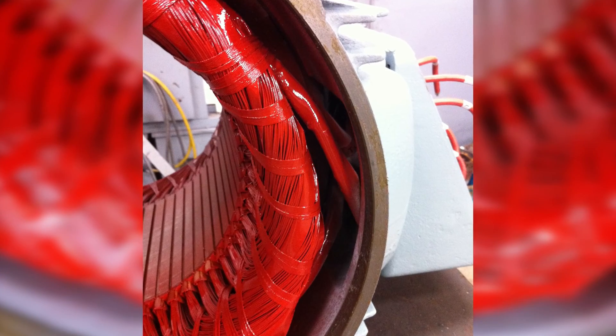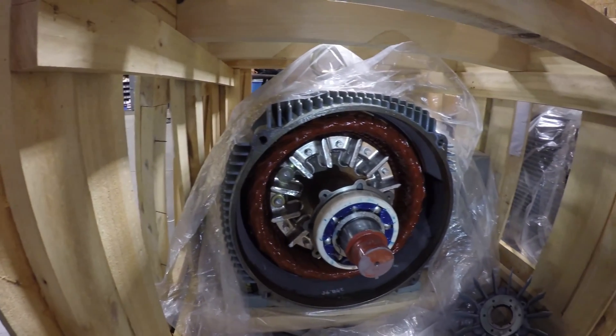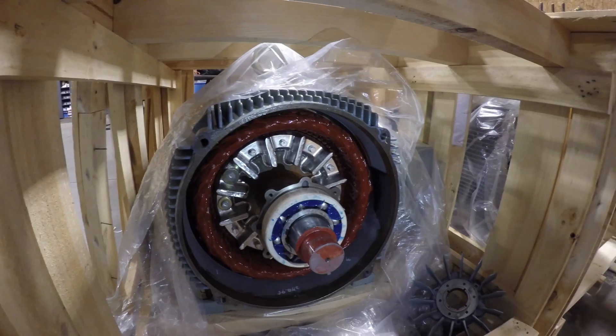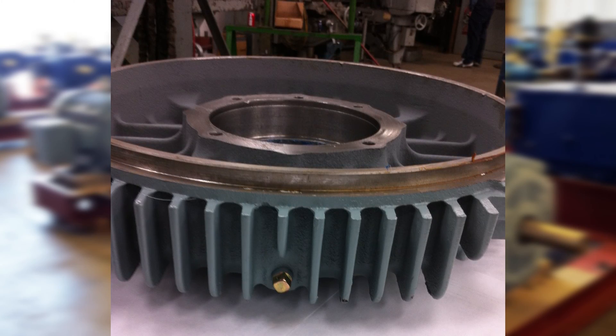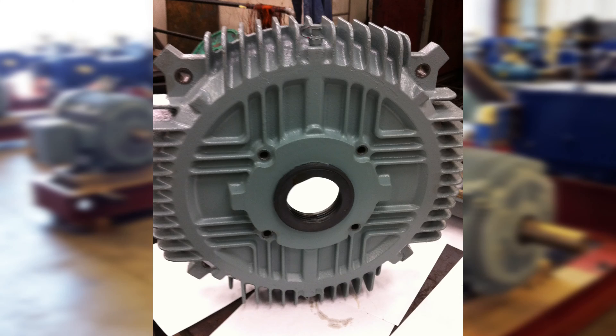Class F insulation with Class H varnish protects the windings in ambient conditions up to 55 degrees Celsius. All bearings are oversized and re-greasable. Stainless steel condensation T drain plugs on the drive end and the opposite drive end.